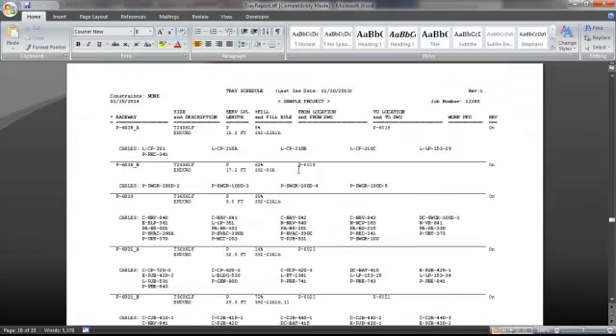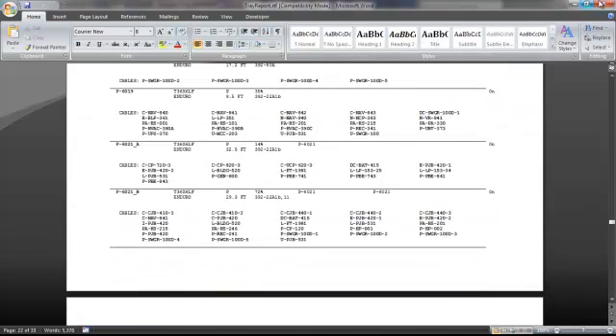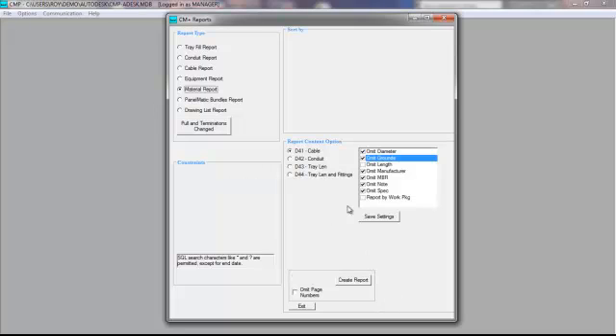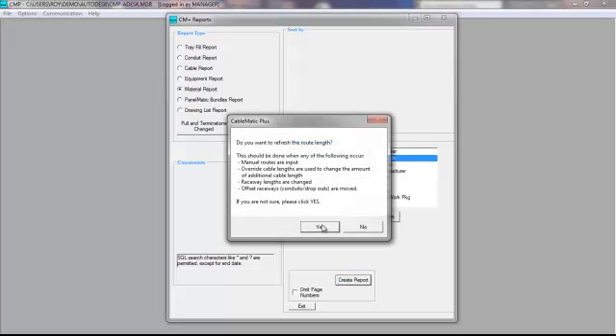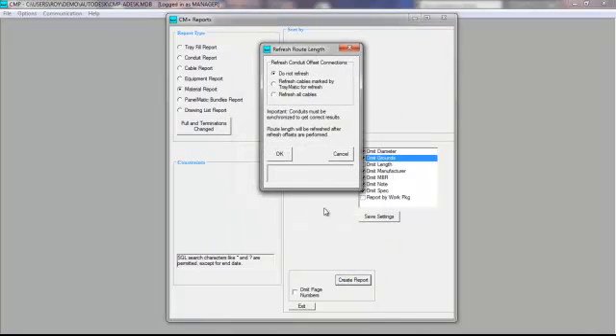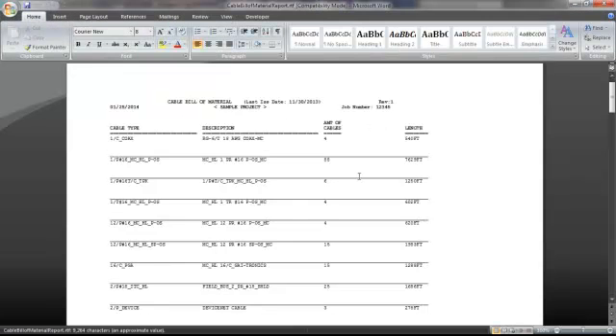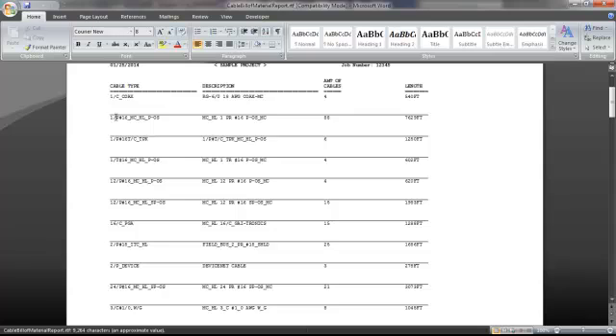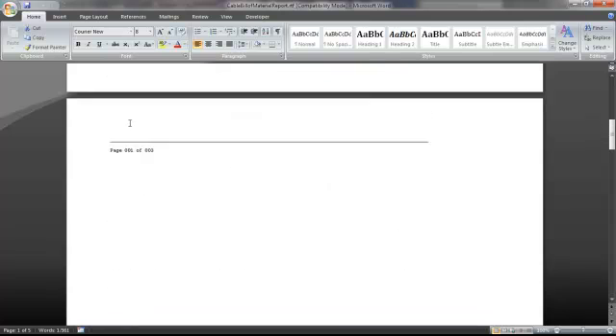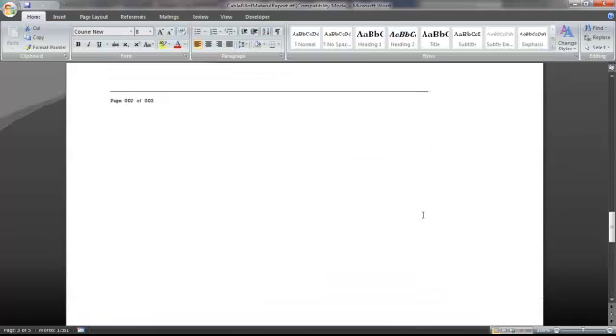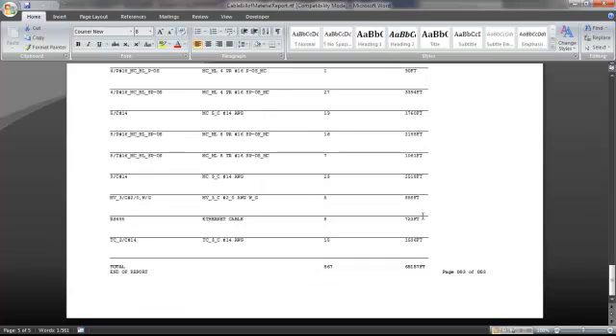Our material takeoffs, we can get a list of our cables. In this case we've got a single pair number 16. We have 7,629 feet of single pair number 16. There are actually 88 runs or 88 cables that use that particular cable spec. If we scroll down to some of the bigger cables, a three conductor 250s, we've got 4,300 feet of that. There are 39 cables that have that particular spec in our cable schedule. So this gives you the number of cable runs you have as well as the total length of cables. It's just another one of the material takeoff reports that's available in the software.